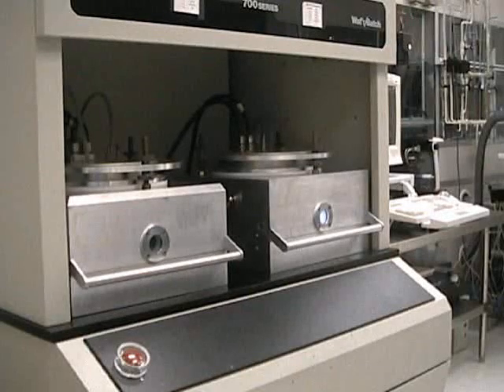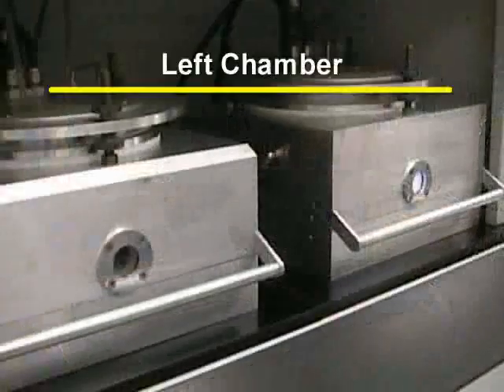PECVD, or Plasma Enhanced Chemical Vapor Deposition System, reacts gases in a RF or radio frequency induced plasma to deposit materials such as silicon dioxide and silicon nitride. This PECVD has two chambers.